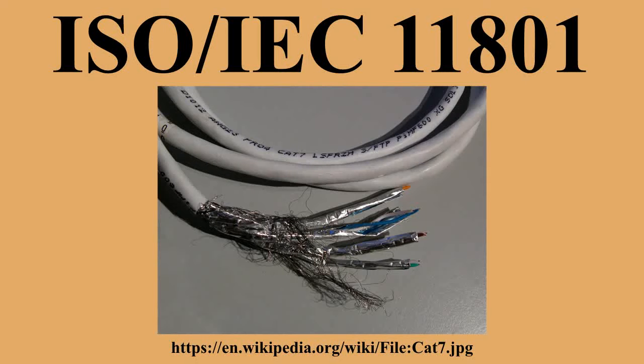OM-3: multimode fiber type, 50 micrometers core, minimum modal bandwidth of 2,000 MHz·km at 850 nanometers. OM-4: multimode fiber type, 50 micrometers core, minimum modal bandwidth of 4,700 MHz·km at 850 nanometers. OS-1: single-mode fiber type, 1 dB per kilometer attenuation. OS-2: single-mode fiber type, 0.4 dB per kilometer attenuation.